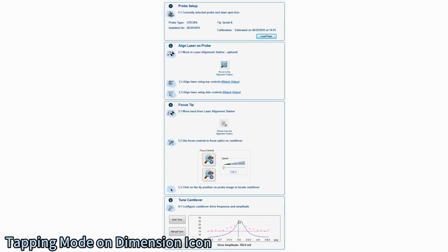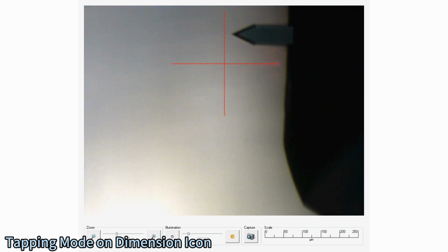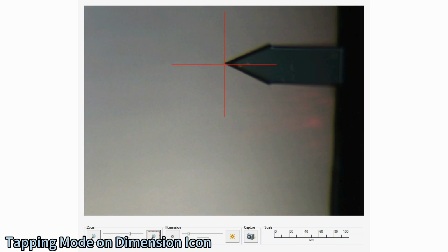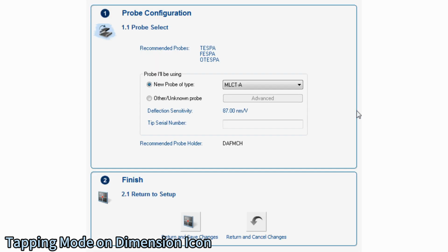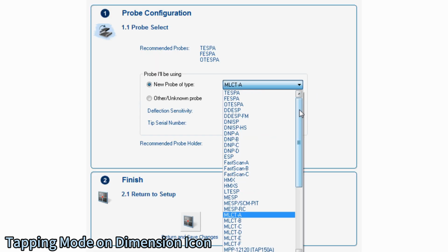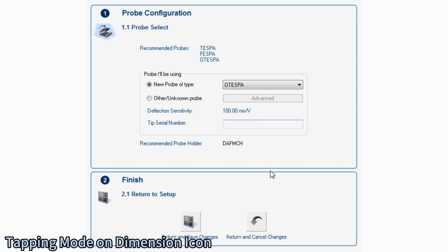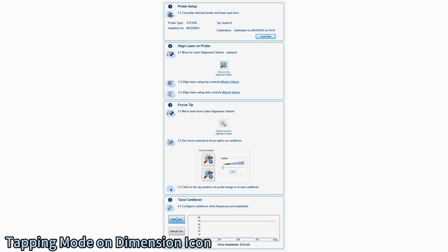From the setup interface, adjust the focus and illumination as needed to bring the probe clearly into view. Center the crosshair on the end of the probe to assure concentric tracking of the optics as the zoom factor is increased. Use the Load Probe command to select the appropriate profile for the probe you are using and save the selection. From the bottom of the setup interface, click the Auto-Tune button to initiate the frequency sweep process that isolates the resonance frequency and optimizes the amplitude value for the probe.